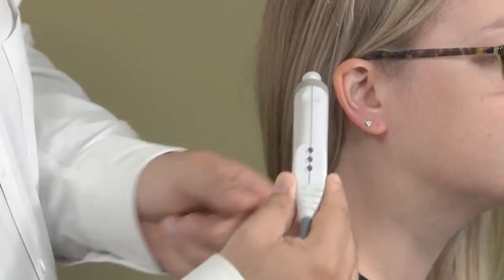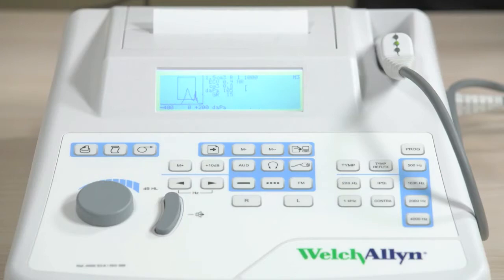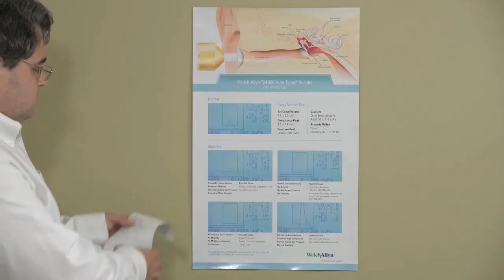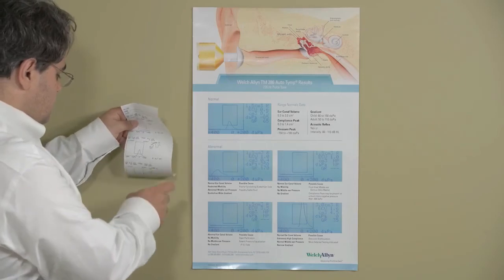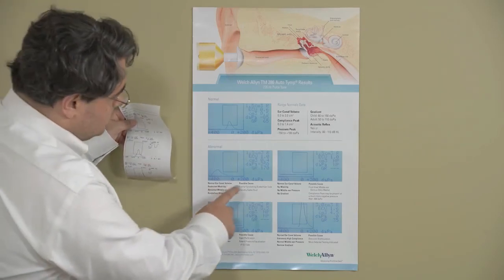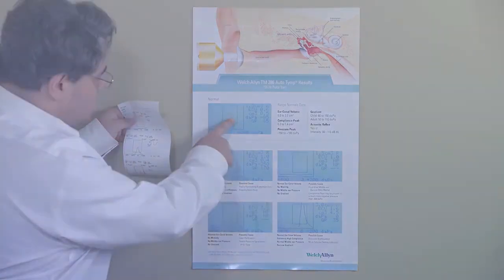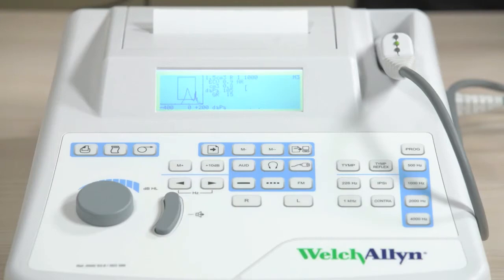You can now remove the probe from the ear canal, and the results will display on the device screen before printing. When reviewing and interpreting results, refer to the Tympanometry reference poster included with your device. The device will not show pass or refer, so the tester will need to understand the results. The test results are stored automatically in memory.